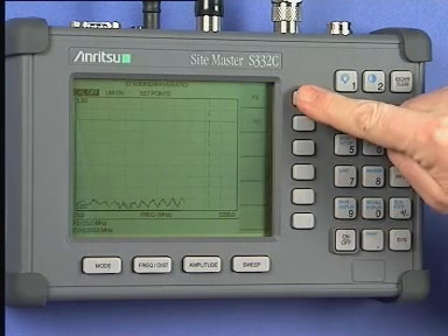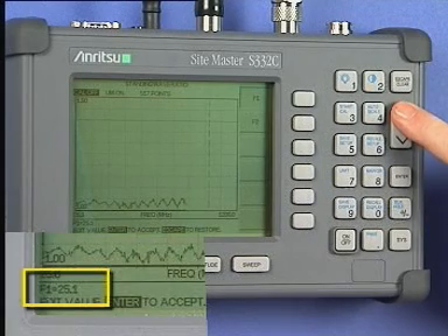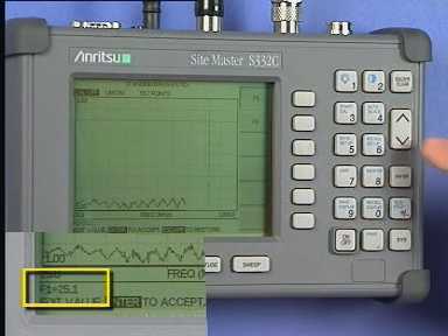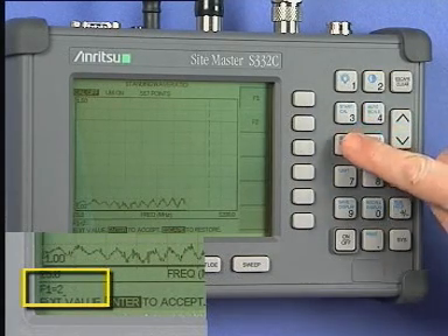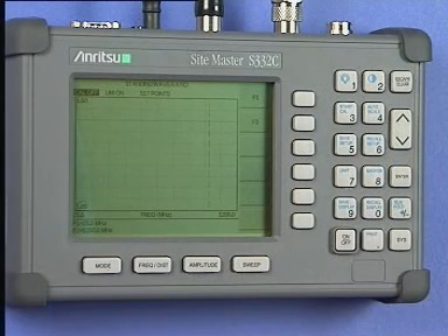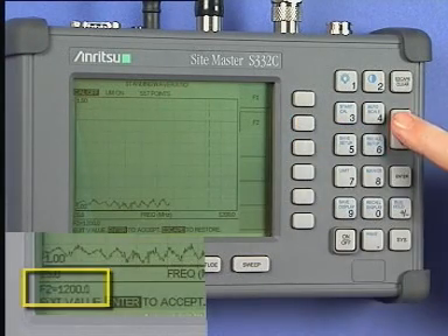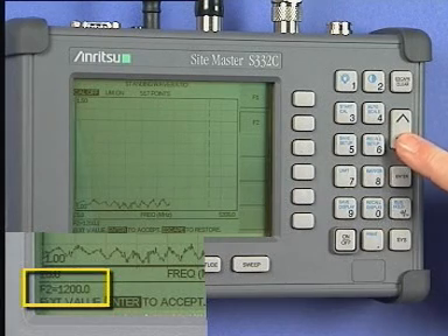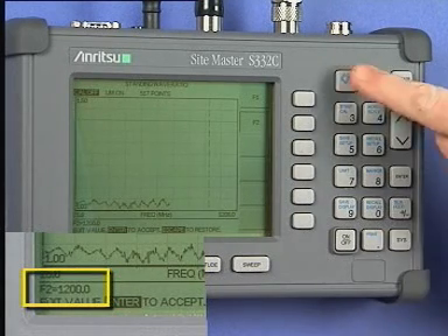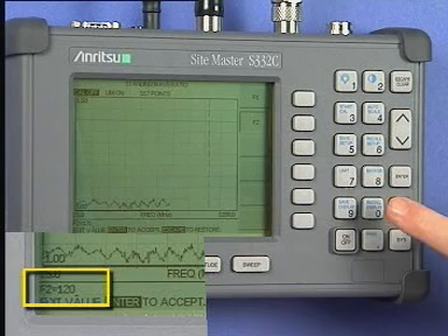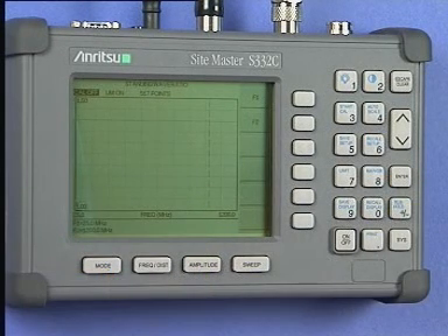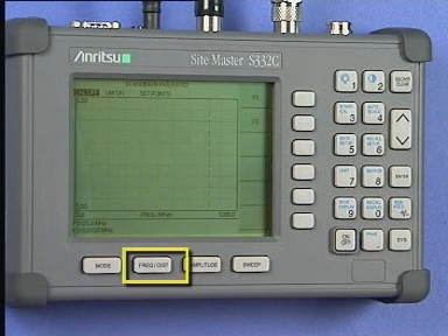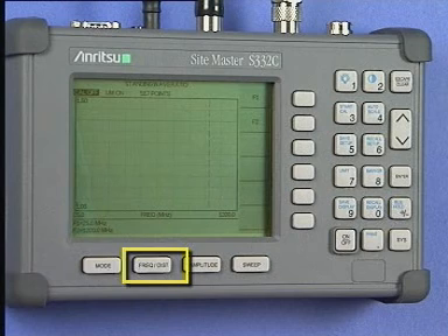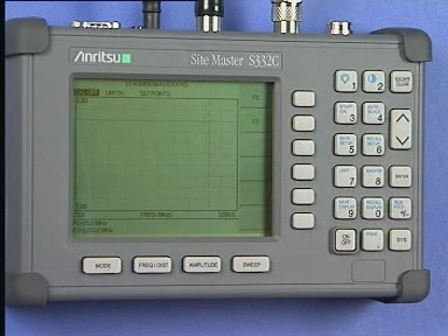You may use the up-down keys to step the frequency displayed, or you may enter the digits on the keyboard. Press Enter to save the change. Press the F2 soft key and enter the upper frequency limit. This will be 1200 MHz. Press the Enter key to save the change. At any time during the forthcoming tests, you may press the Frequency Distance key to view the F1 and F2 frequency limits, which are displayed at the bottom left quadrant of the instrument's screen.